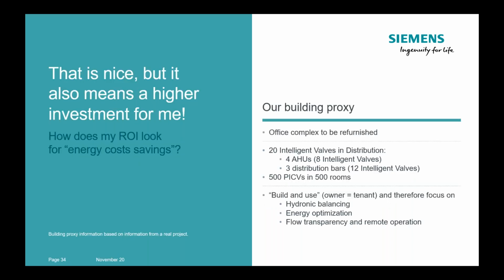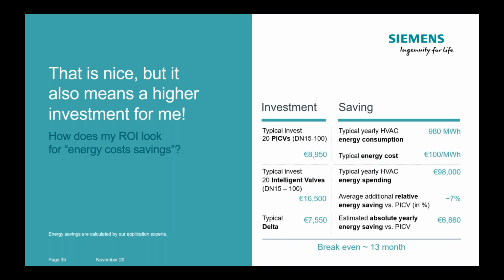An intelligent valve solution. Let's assume the building Luca mentioned, 500 rooms with 500 PICVs and 20 valves in the distribution area, some valves for air handling units, some valves for distribution bars, for distributing to the fan coil solutions there. If we assume this and we have a traditional installation with PICVs for these 20 valves in the distribution, we would assume an investment of around about 9,000 euros. On the other hand, if we do this with the intelligent valve solutions, we have to assume a higher investment cost, like shown here, around about 16,500 euros. So we have a higher investment cost of 7,000 euros, 7,500 euros.